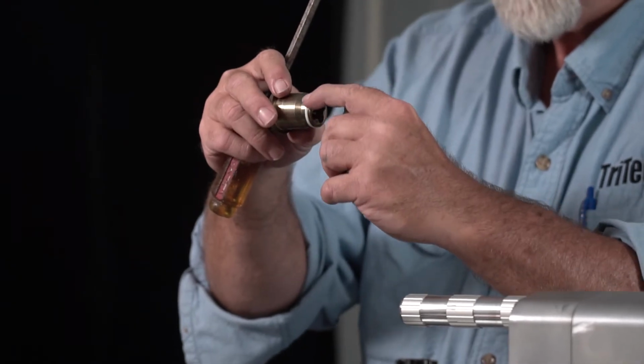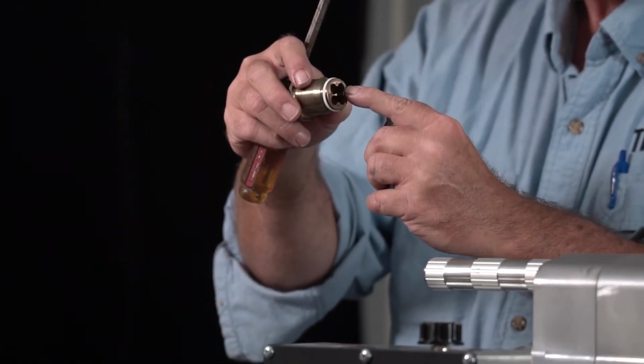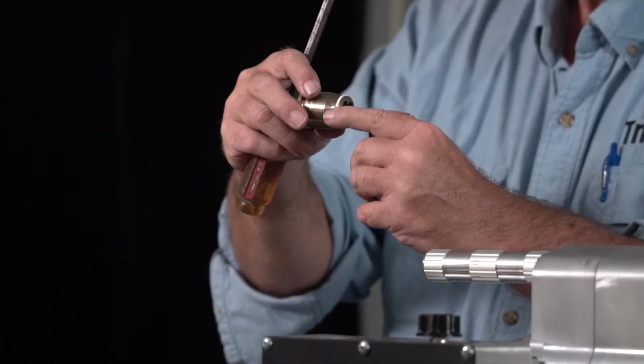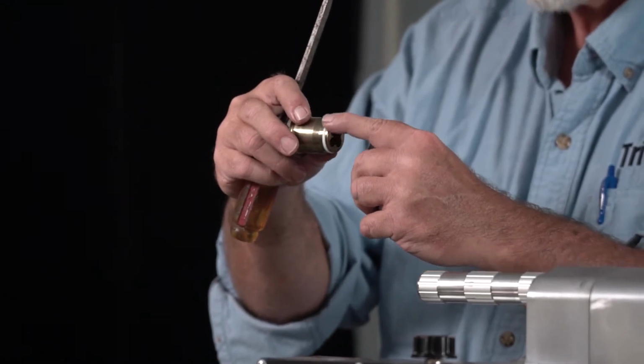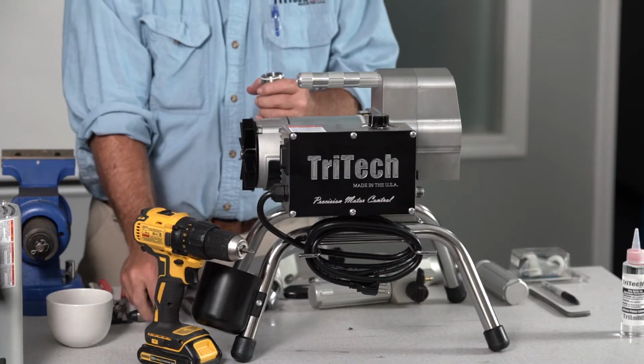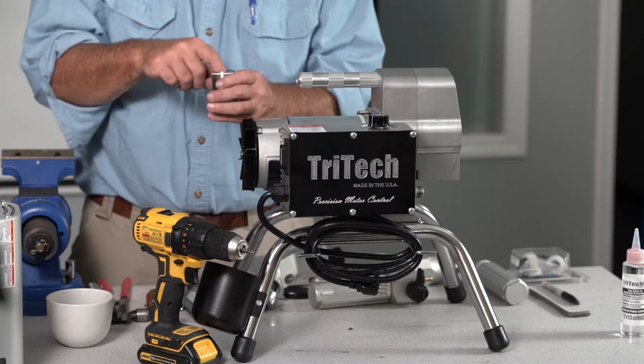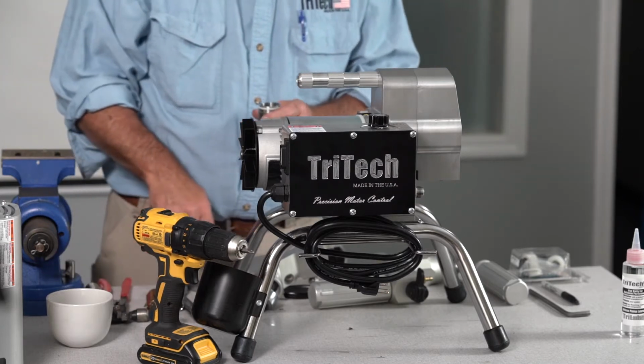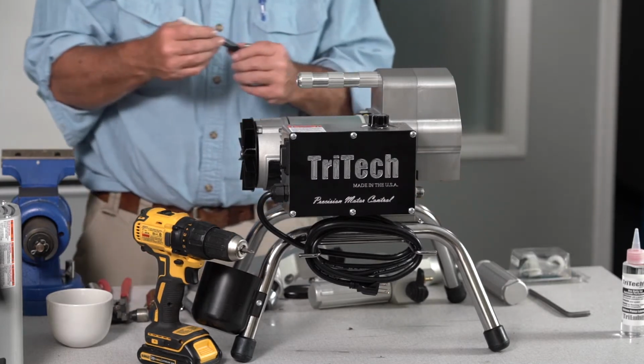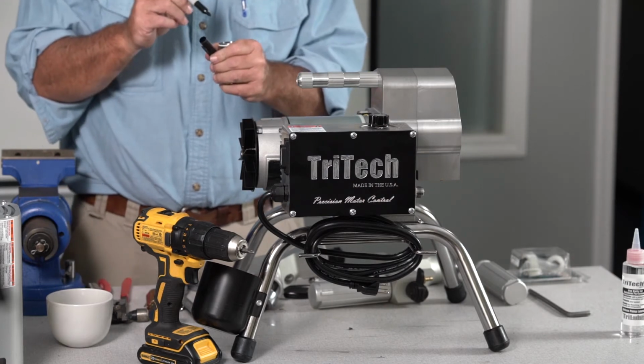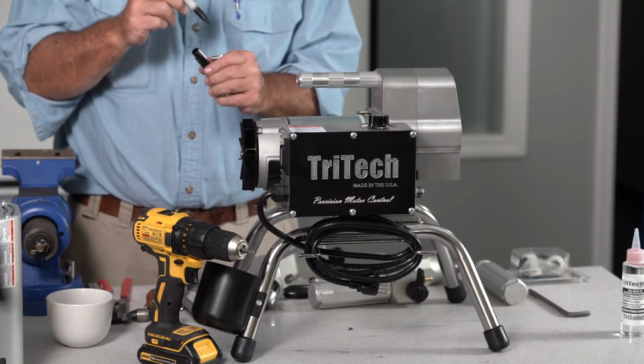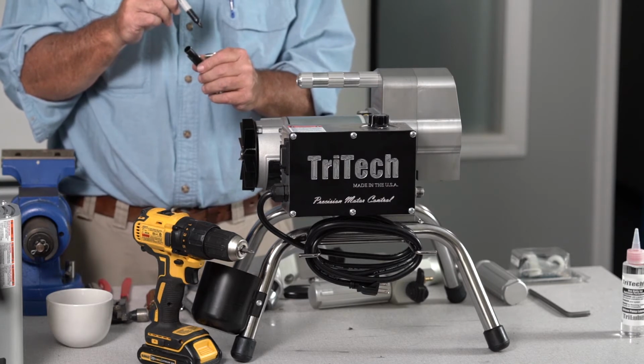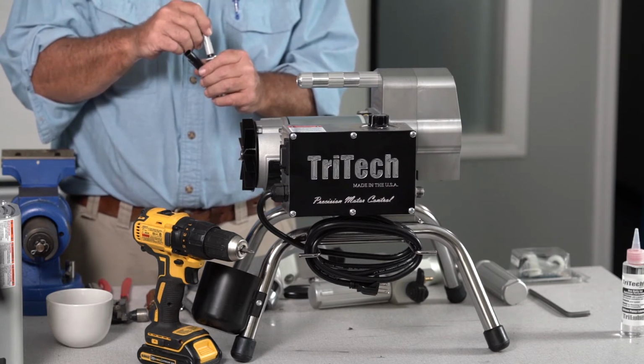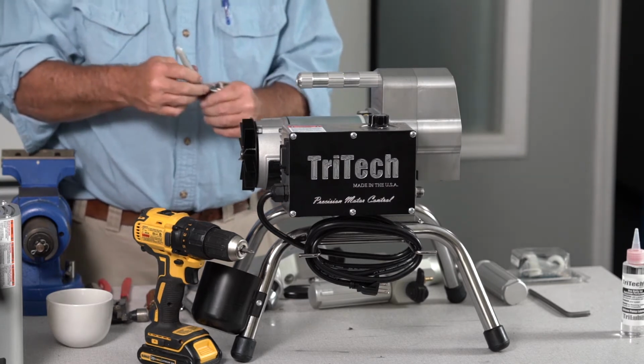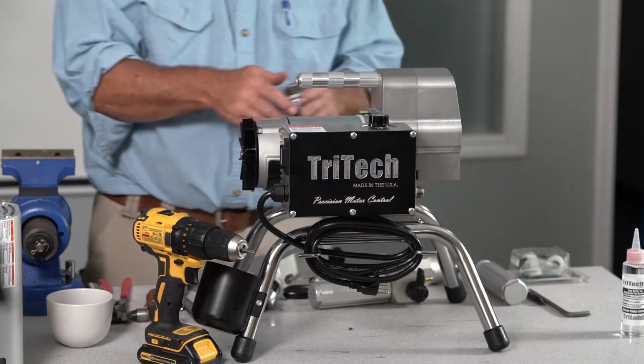You want to examine this O-ring. This O-ring is in the repair kit. If this is worn or damaged, you replace it. If it's not, it's good to reuse it. Before you remove your ball and your seat, you want to mark your seat with a Sharpie so you know what side was up when you take it out, because you're troubleshooting what the problem could be. So I just make a little mark, and so you know what side of the seat is up.